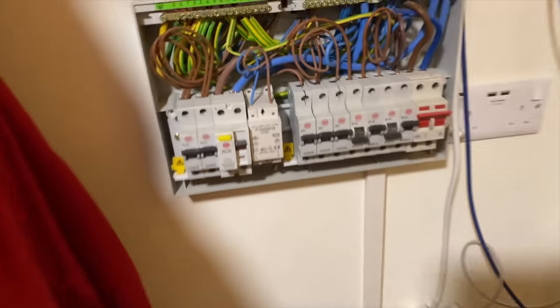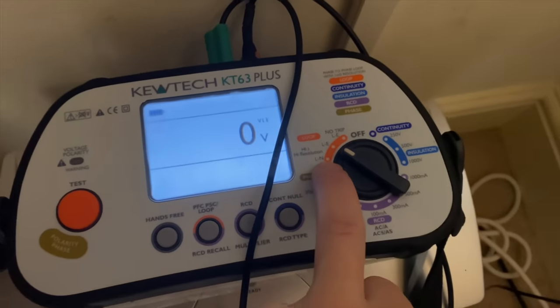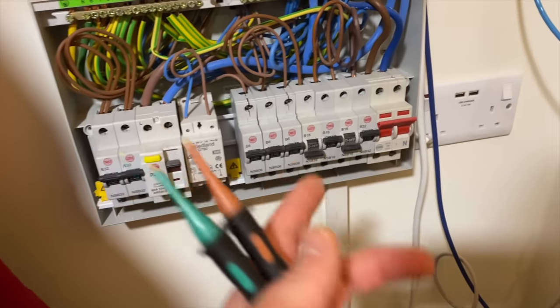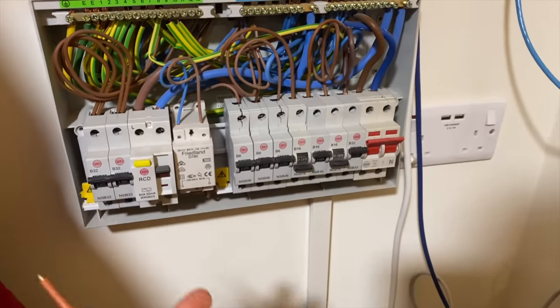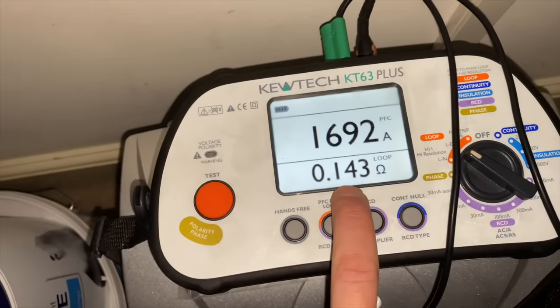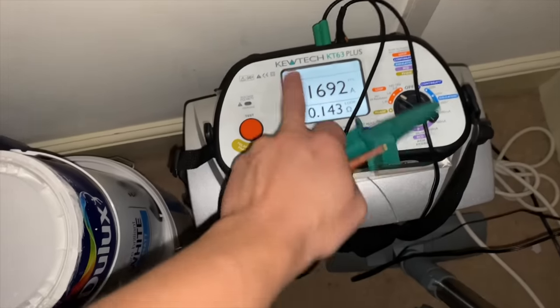We're going to isolate the board in a second to do a Ze and a PFC at the board. We've just done the nominal voltage — 241V. With my Kewtech KT63 you can do two probes: live-neutral and live-earth, no need for three leads. The Ze came out at 0.14Ω with the installation isolated. Then 1.7kA for the PFC. I've got a feeling it's going to be PME — I'll go and confirm that.